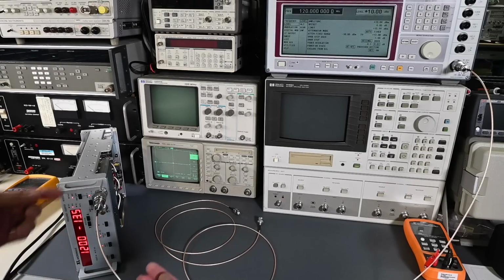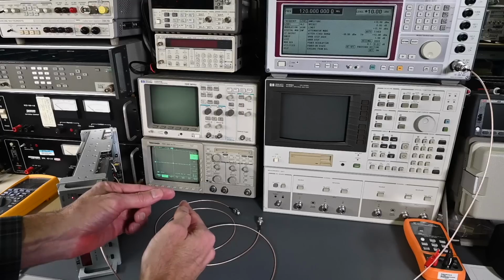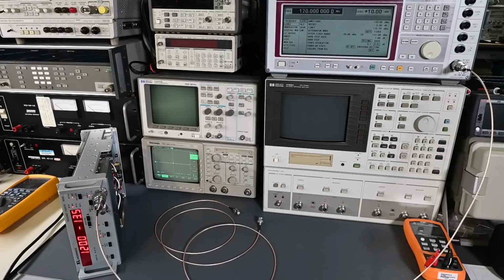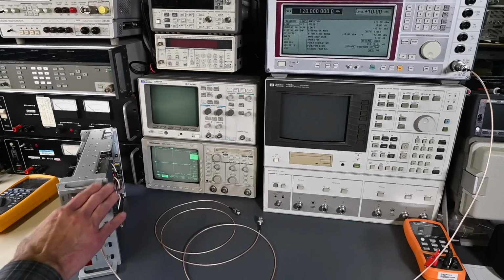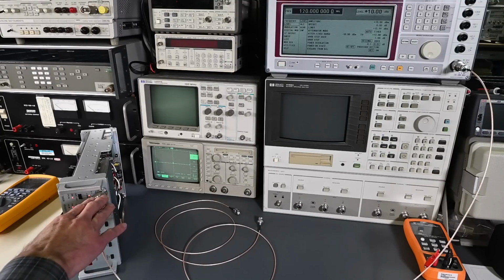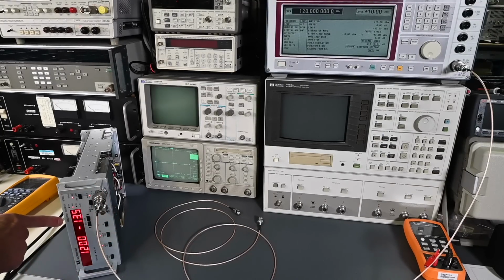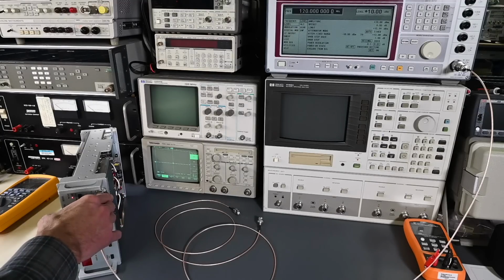So the plates of the capacitor would be the conductor on each side, and the gap in the middle, the air, is the dielectric. So it's a classic sign that when you have an open circuit, the higher the frequency, the more signal you will get going through, and the higher the frequency, the better the signal will pass. Because again, capacitors will pass an AC signal. So I believe the input on this has a problem and that there's an open circuit, and that's why we're getting this very unusual reading. I don't think the power meter is wildly out of spec on its calibration. Maybe it does need some calibration, but I think really the issue is an open circuit.